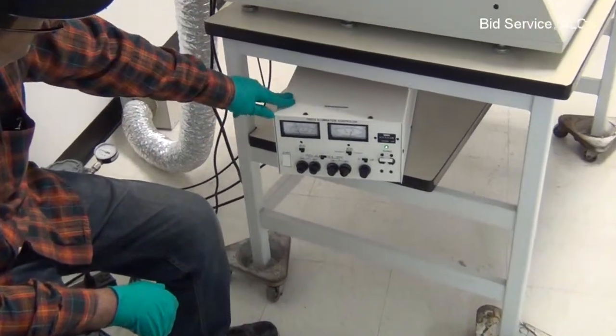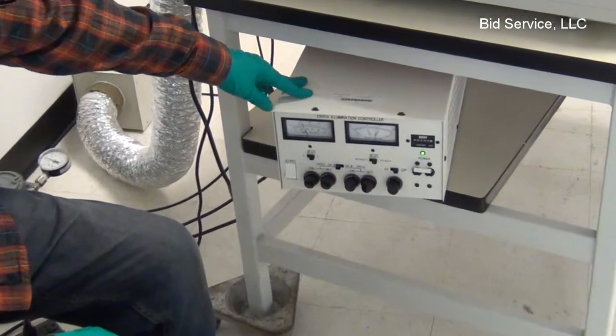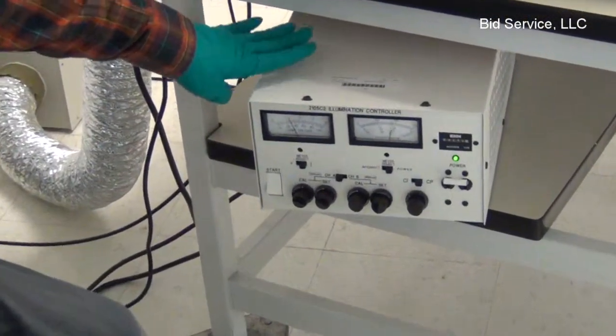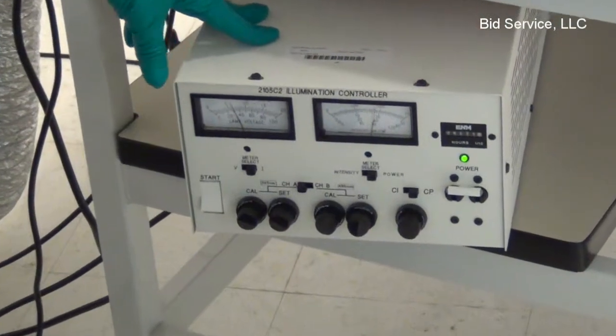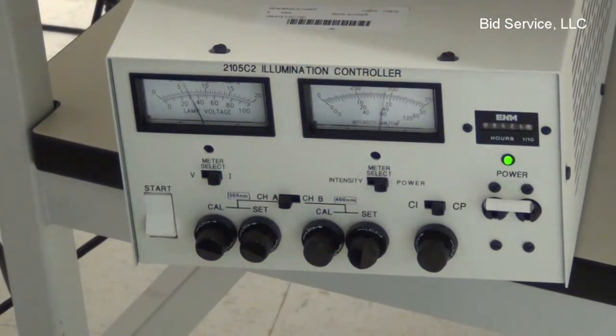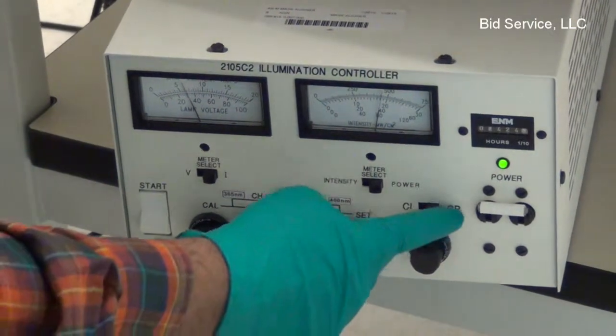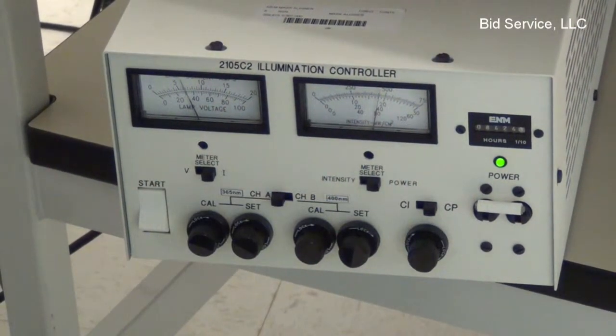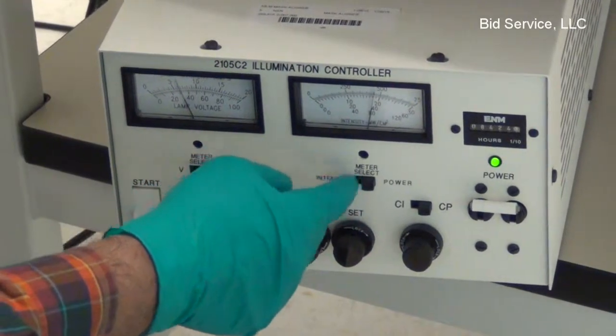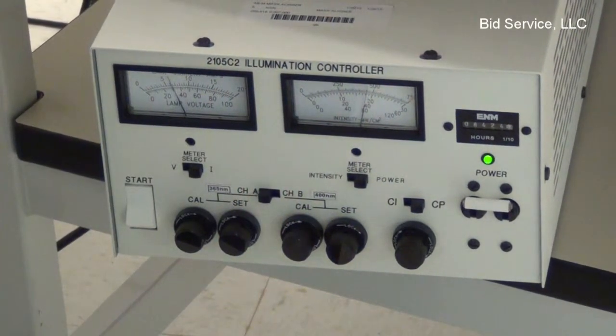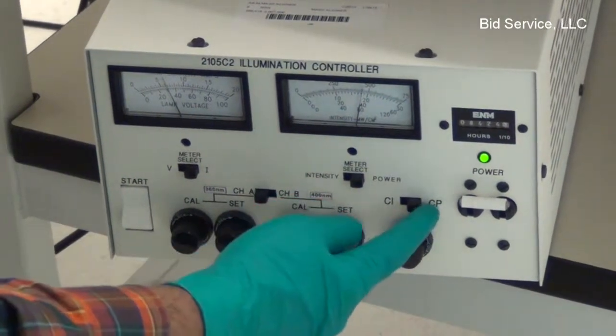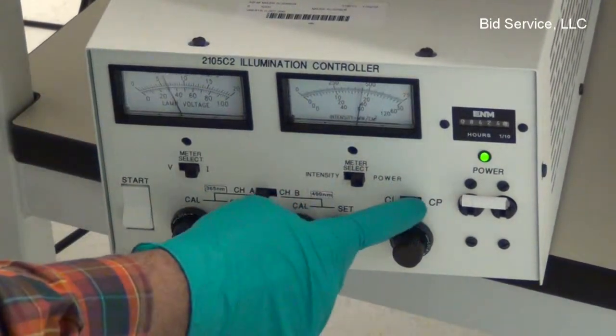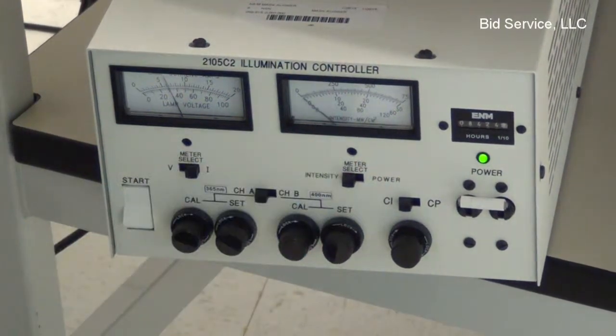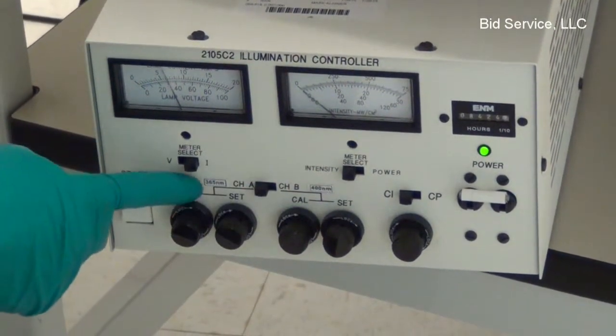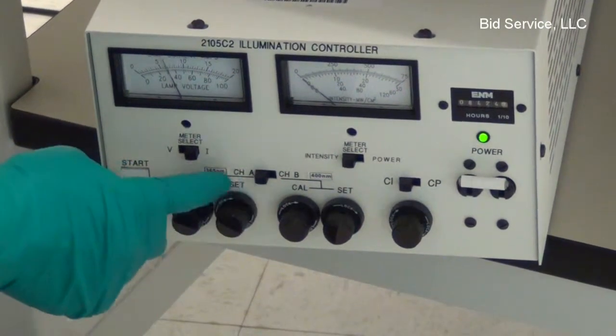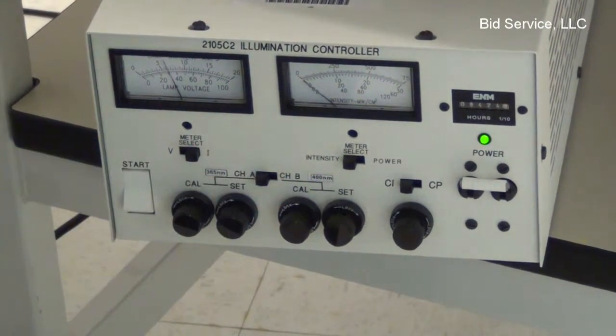UV lamp is powered by this illumination controller, 2105C2 controller, currently configured for 500 watts UV lamp. The unit can be used in constant power mode or constant intensity mode. Right now it is in constant power mode. I set it about 450 watts. If the unit is to be used in constant intensity mode, slide the switch to the CI mode and intensity, and there are two channels, one for 365 nanometer, channel A, and channel B is for 400 nanometer.